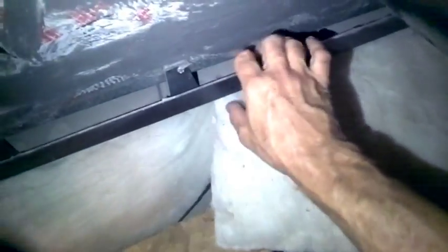All the ducts look well intact and with no real kinks. Everything's strapped. Flue is safe and good. One thing we look at is the flue vent here. You want to make sure you have proper clearance from any wood or flammable material, and you want to make sure your system's level and the drain pan there. You know, looking at the drain pan here, you see all this dust, so that's a good sign and an indication that the primary's doing its job and collecting all the water. All the seals are good.